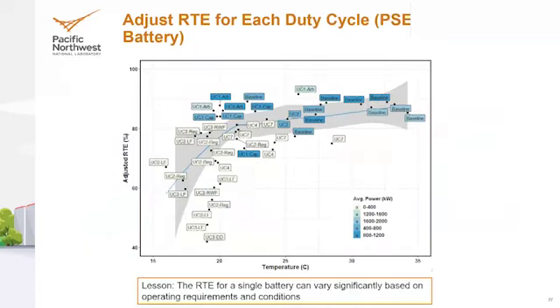We also found the round-trip efficiency for even a single lithium-ion battery system could differ quite significantly. Here's the Puget Sound Energy battery system, and you can see the round-trip efficiency falling quite low for a very specific set of tests, and then rising up towards 90%. It varies mostly based on temperature and the type of use case you're using. Some cases have a lower power output level where auxiliary loads are a larger share of the overall round-trip efficiency calculation, and at low temperatures it tends to yield lower round-trip efficiencies.